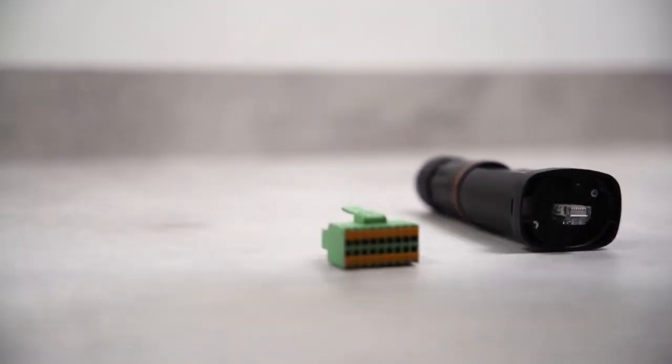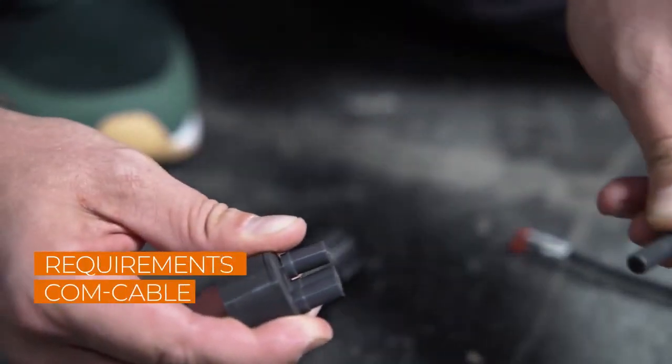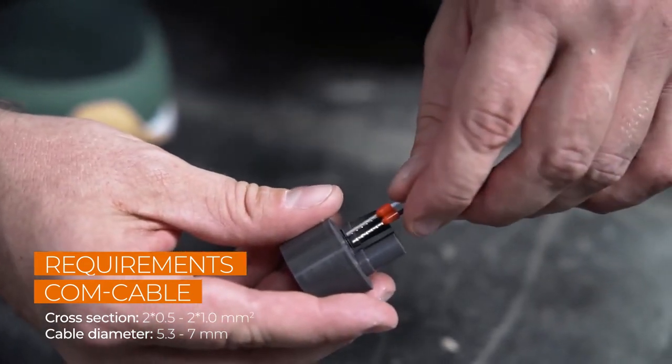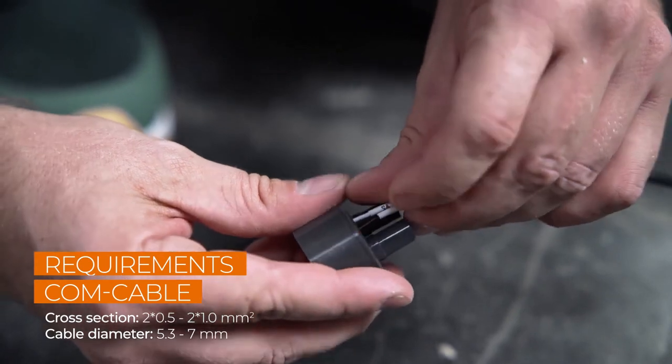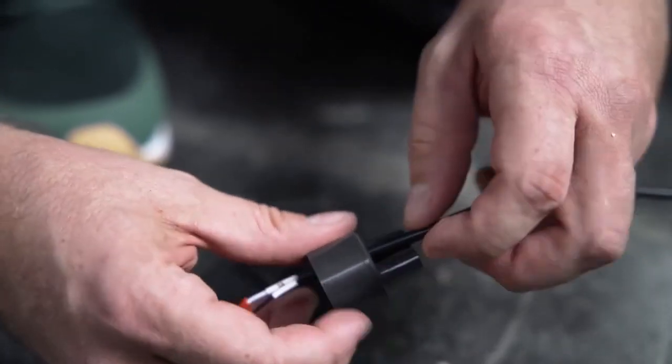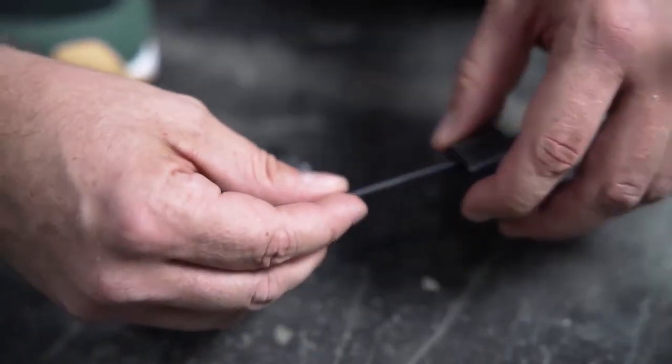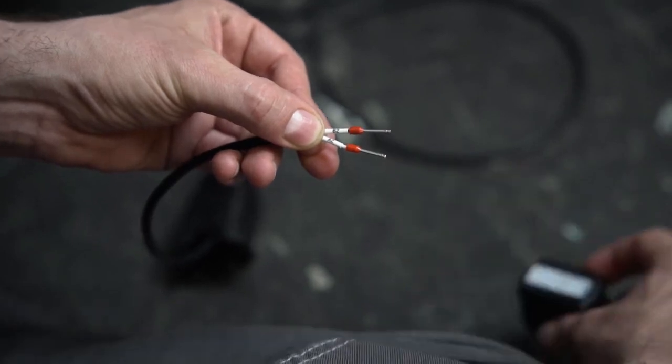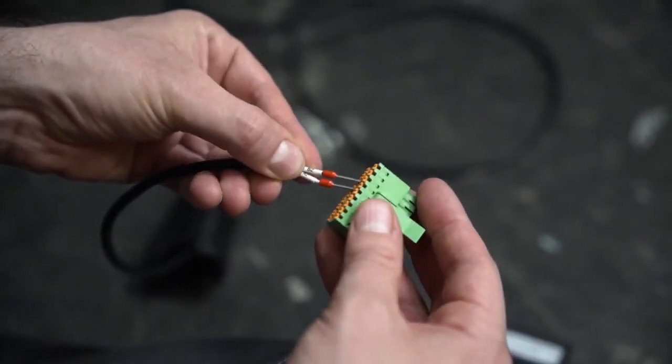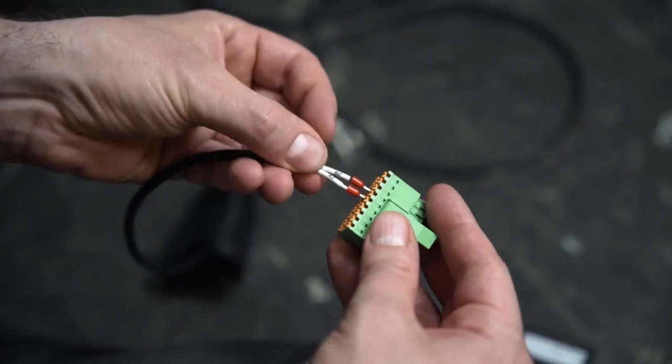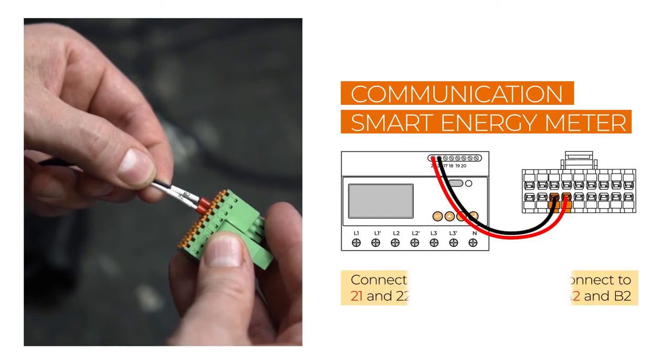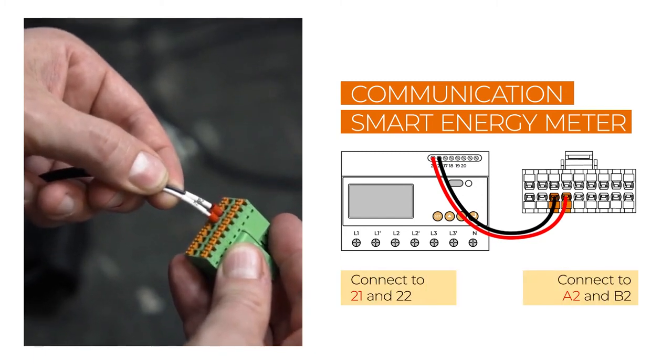In the next step, we will set up the communication port. Via this port, you can connect the smart energy meter or the communication cable for daisy chain mode. Let's start with the energy meter, which is needed for the feed-in power function. Remove approximately 4 to 5 cm of the cable sheath of the communication cables. Then strip approximately 7 to 10 mm off the inner cables. If necessary, you may have to fit the cables with end sleeves before you push them into the plug.